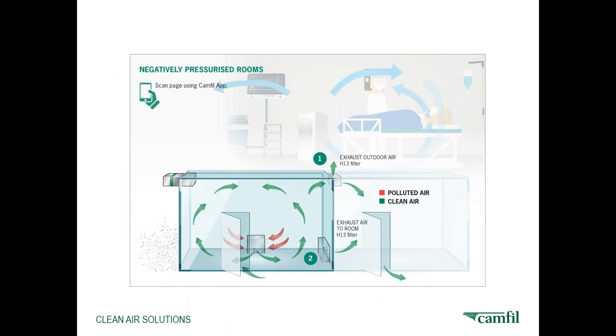In this picture, I'll explain how we can create a negatively pressurized room and its effect. Instead of supplying air to the room as in positive pressurized rooms, here we exhaust the air to create the negatively pressurized rooms. In hospitals, creating negatively pressurized rooms is a key requirement to protect the health of hospital patients and staff or sterile equipment. As the air in a negative pressure room is often hazardous to other patients, the idea is to take the contaminated air from the room, clean it, and distribute the clean air to a non-critical area.